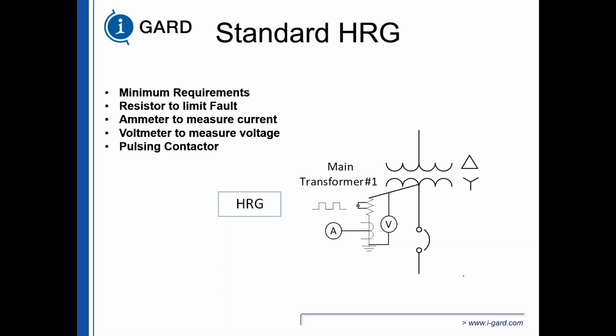Now, a lot of manufacturers are going to say they have communications and data logging. So let me give you an example of what standard HRG is going to give you in terms of data logging and communications. You have a fault. You don't have a fault. You have a fault. You don't have a fault. The fault is here. The fault is not here. That's what you're going to get in communication, because the only thing you're looking at is the current going through the resistor, or the voltage from the neutral point to ground. That fault can be anywhere in your facility, and data logging or communications on standard HRG is like saying when you have a headache: you have a headache, you don't have a headache. You don't know how to get rid of it, but it's there.